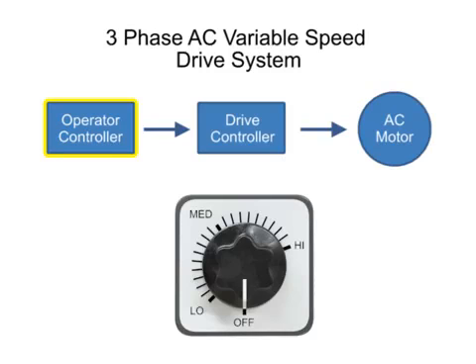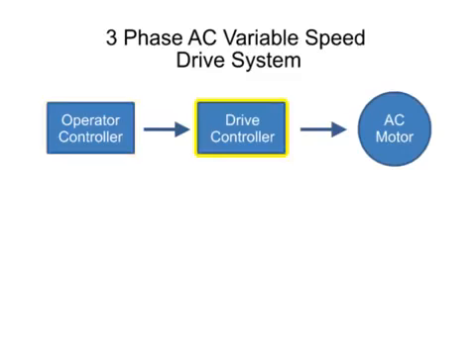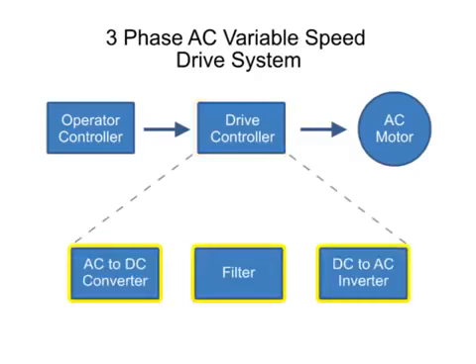An operator control device provides a means to start and stop the motor and adjust the operating speed. The drive controller consists of a variety of components that work together to convert an AC input into a frequency and voltage output necessary to change the speed of an AC motor.